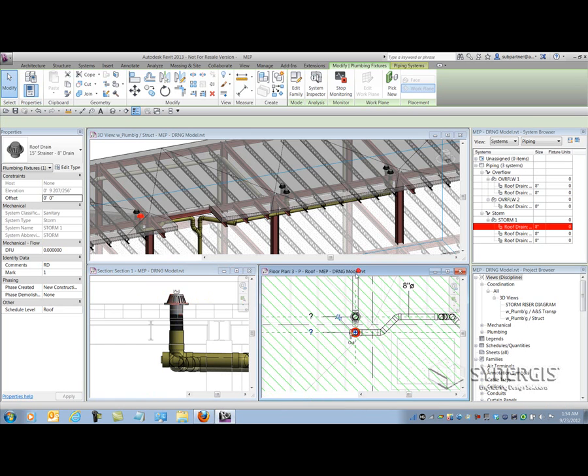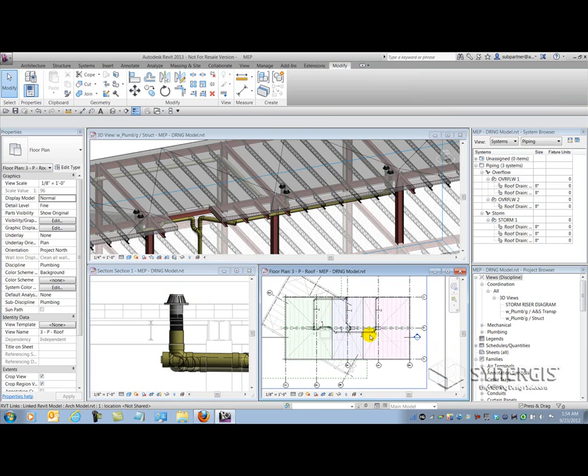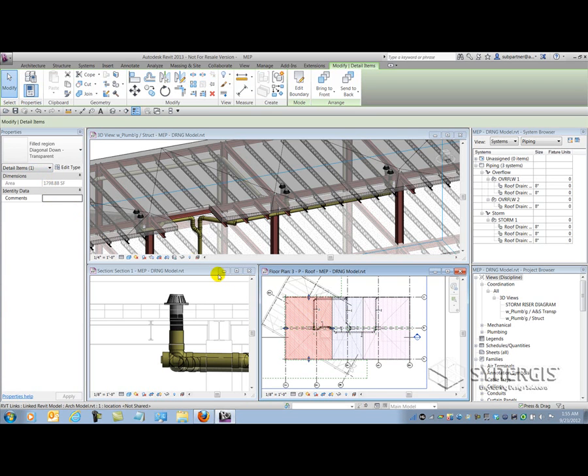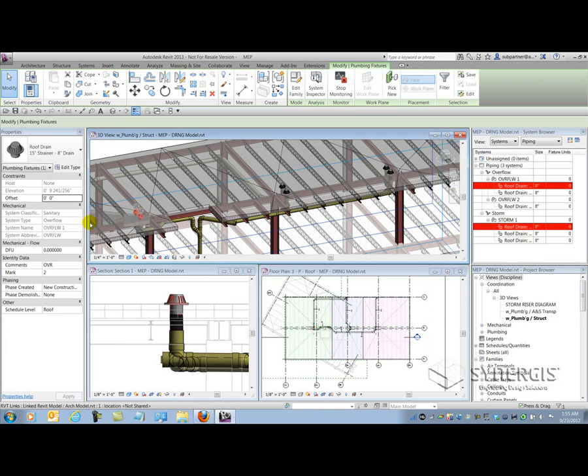Now let's take a look at the plan view, which is going to help me look at the roof surface and analyze how much coverage each drain is going to handle. I can see how the architect has pitched the roof. To get the square footages, I put in a filled region — each zone has its own filled region. Why filled regions? Because they give me the square footage of themselves in the instance properties. That allows me to input them into the drains. So I pick a zone, look at the square footage value, come into the model and pick the two drains in that zone. I input the value I saw for the filled region, which is 1789.